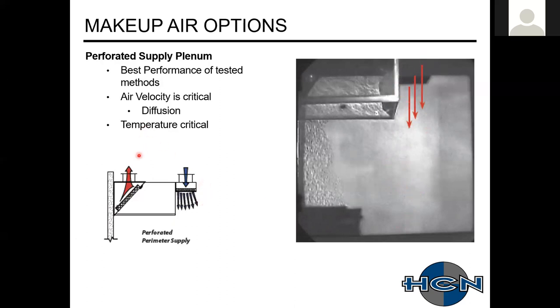So the big thing, like I said, is that your air velocity and your temperatures are very critical with this. Typically, you're looking for a 24-inch tall hood. You have a 6-inch plenum, and 18 inches from the bottom of that plenum to the bottom of the front lip of the hood. You want that running right around 140 to 150 feet per minute.